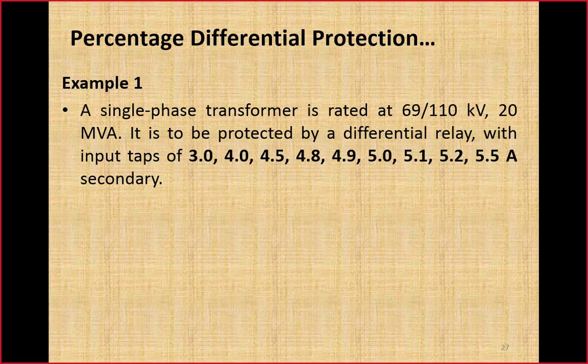Now it is important to understand what is meant by the tapping of the relay because a differential relay does not have these tap settings. But remember, the differential relay that is designed for the transformer has this type of tap setting. So we are talking about an electromechanical type differential relay. But nowadays the digital differential relays have made this detection of fault or application of differential relay for transformer much easier because this tap setting will be inside the setting. No need to have the physical taps.